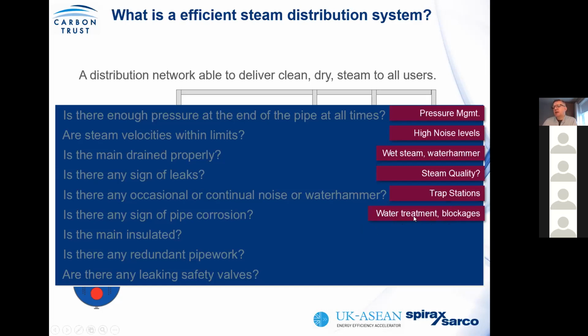Not only may it cause traps to fail open, but where you have pipe erosion due to poor water quality, you might find that traps fail closed. And you could say, oh, a failed closed trap doesn't lose energy, but it increases the likelihood of water hammer. It retains water in the system. And 1-2 millimeters of water on the heat exchanger can reduce heat transfer efficiency by as much as 10%. So in other words, you could then find that you're using a lot more steam. You have to operate the heat exchanger at higher pressure. Higher pressure means higher pressure condensate. Higher pressure condensate means higher flash losses at vented condensate recovery systems. So in other words, it has a compounding effect.